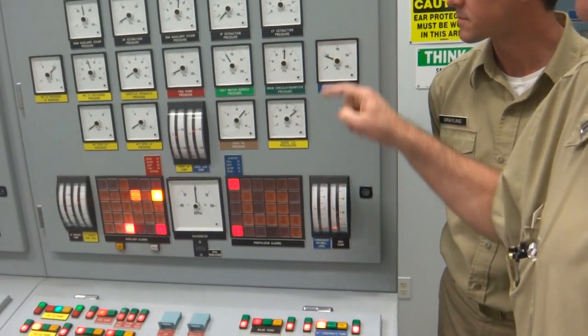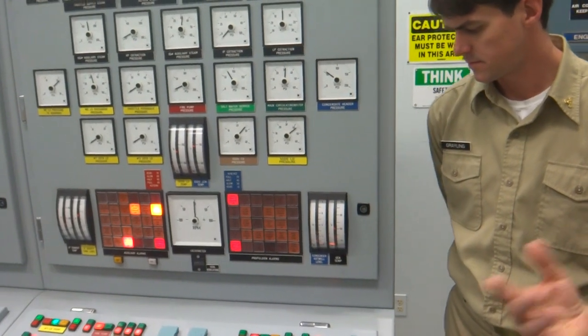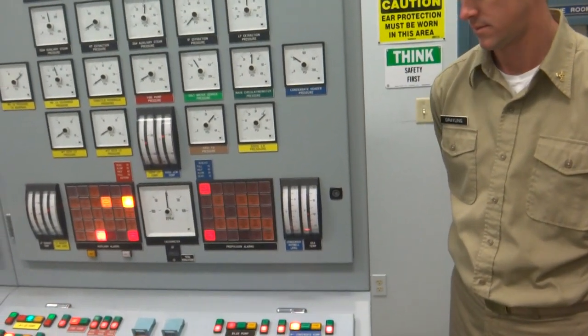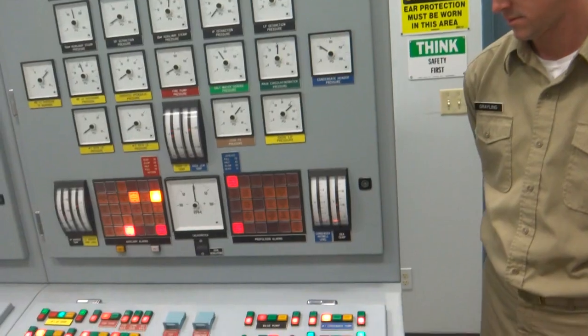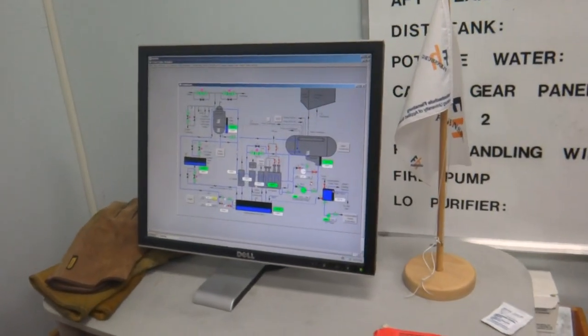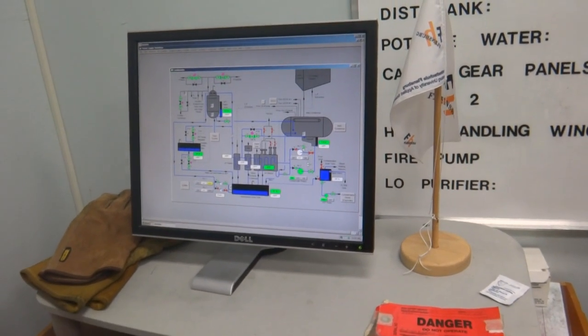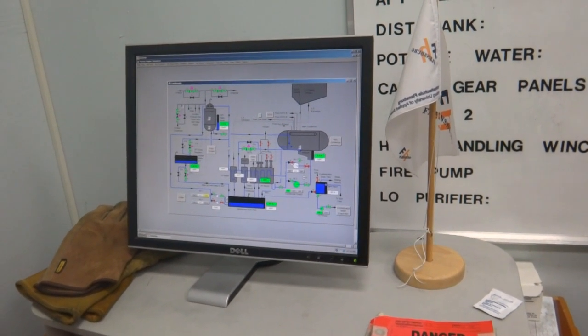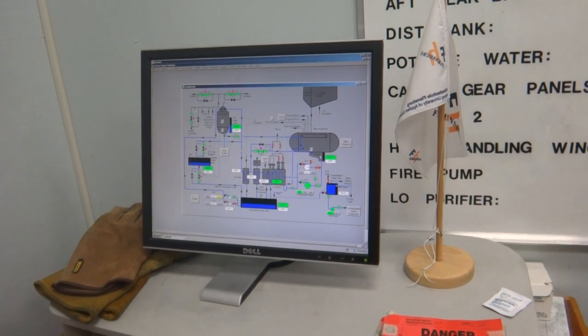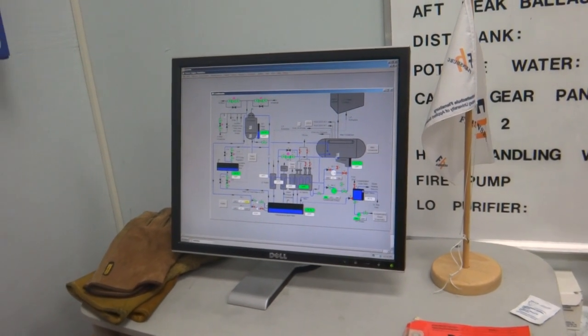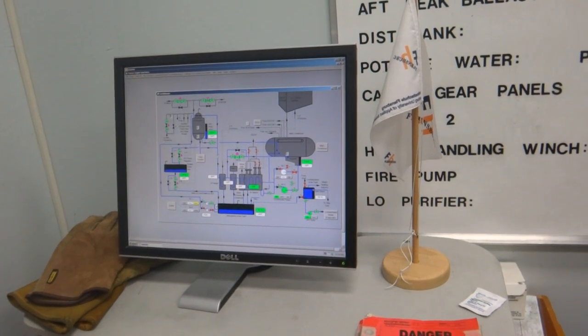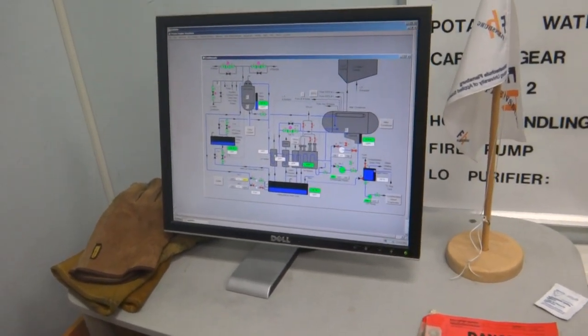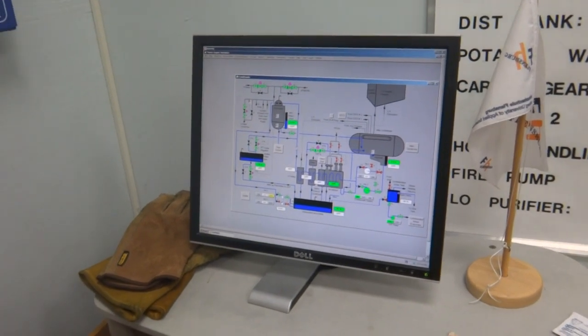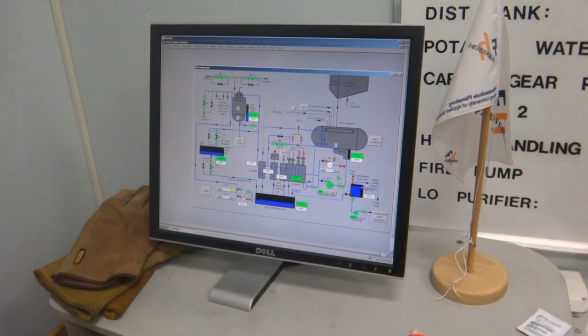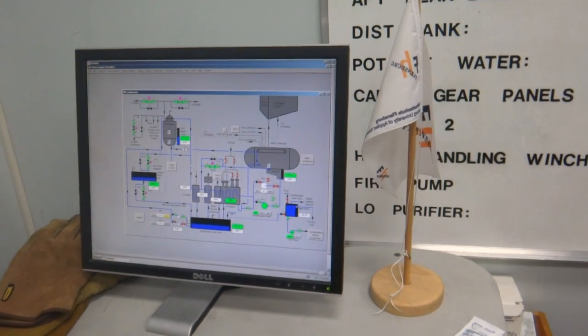Now we got it. And you'll see it bounce because it's going to be intermittently losing suction. That's normal for a real condensate pump in port. It's hard to get enough suction. So we got that, and I'll open up the vent line on this one and shut the vent line on that one. So we're good there. Now we're recirculating, it's cooling, coming back, going through. And what's the condensate doing when it goes through all these heat exchangers? It's getting warmer, isn't it? So we've probably got enough condensate, 0.9. I'm going to say that's good.